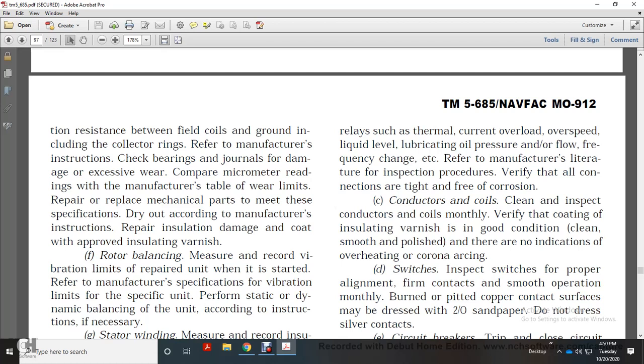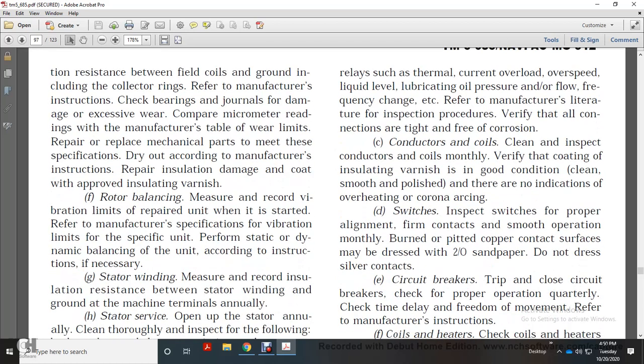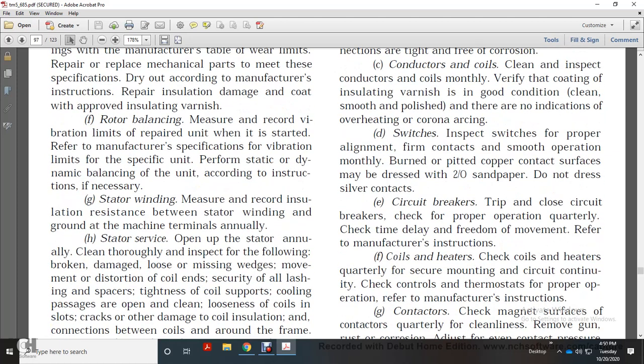Verify all connections are tight and free of corrosion. Conductor coil: clean and inspect the conductor's coil monthly. Verify the coating of the insulation varnish is in good condition, clean, smooth, and polished. There are no indications of overheating or corona arcing. Inspect switches for proper alignment of the contact, firm contact, and smooth operation monthly. Burned or pitted copper contact surfaces may be dressed with fine sandpaper; do not dress silver contacts.